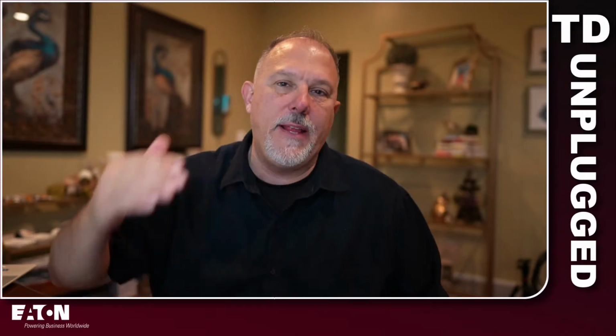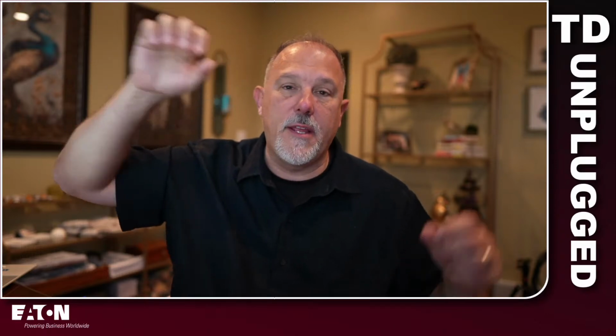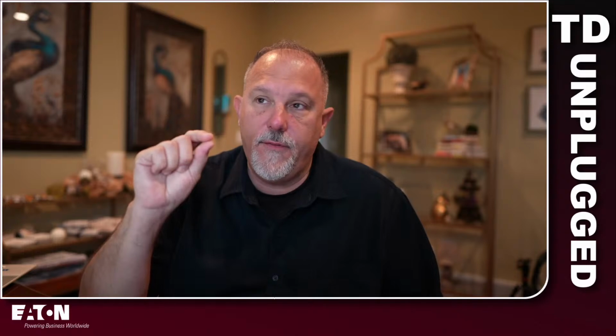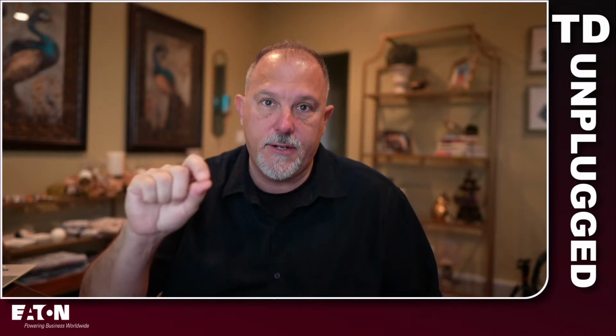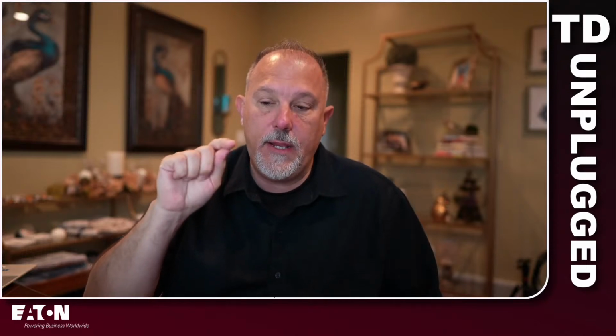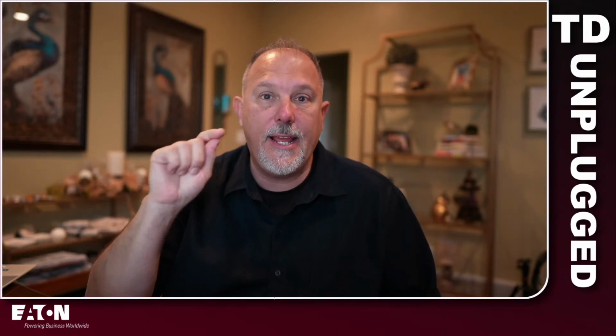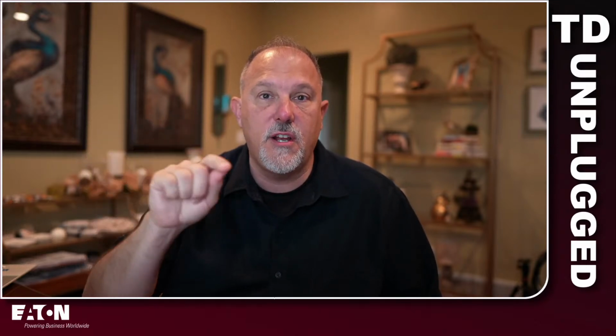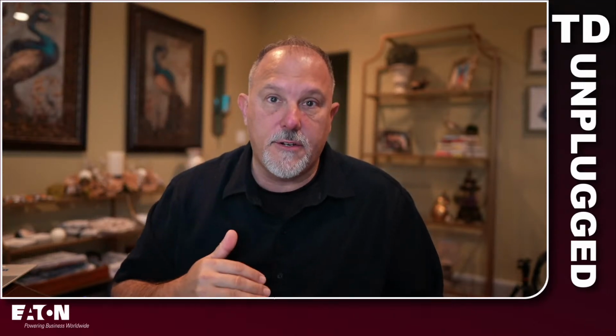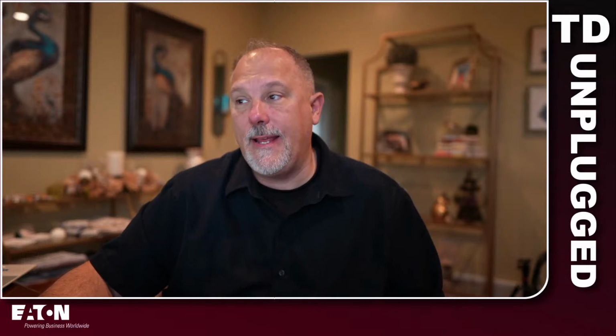And the other comment that was made was that they usually have that guy wire that comes down or something that holds the conductor. Maybe that's what it should say. Maybe in reality, and I thought we had this somewhere, Alan or Steve or one of you guys might know, isn't there a requirement for a luminaire not to be supported by the conductor? Maybe that's what we need in this overhead service conductor application, that the conductor should not support itself. There should be some other method that supports the conductor. I don't know, but in any case, that was oops, I forgot.